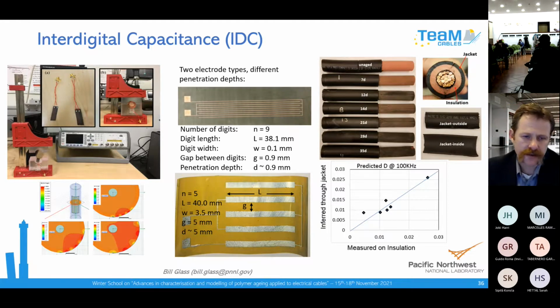We demonstrated, along with colleagues at Iowa State University, and now we're exploring this with University of South Carolina collaborators, that when you have an unshielded cable, by judiciously selecting the geometry of the electrodes, you can actually detect changes in the insulation through the jacket. So you can see changes in the jacket and the insulation just from the outside with these sensors if you don't have a shield.